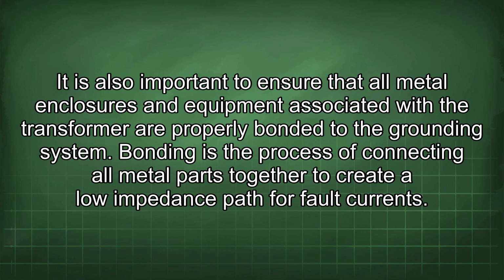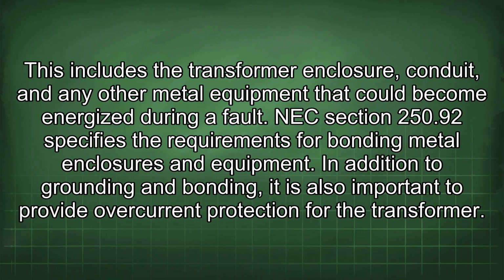Bonding is the process of connecting all metal parts together to create a low impedance path for fault currents. This includes the transformer enclosure, conduit, and any other metal equipment that could become energized during a fault. NEC Section 250.92 specifies the requirements for bonding metal enclosures and equipment.